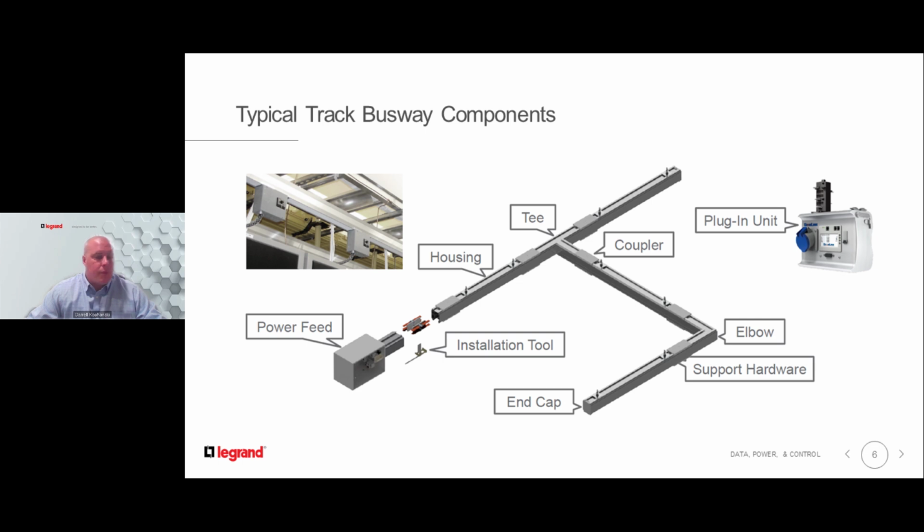But, looking at the options of underfloor versus overhead, both power methods have been used in the white space for several years. But a majority of projects that we're seeing deployed now are going overhead for the reasons previously mentioned. Overhead busway, obviously, for the ease of installation, the usage benefits of busway, and the reliability.